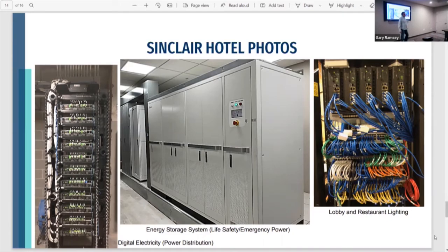Because it's below 480 volts, people think it fits into low voltage, but no, low voltage is under 60 volts by code, and this is 336 volts, so this is not low voltage. This is class 2 power. It generates and runs up to 336 volts. So I never say this is low voltage, I say it's class 2 power.